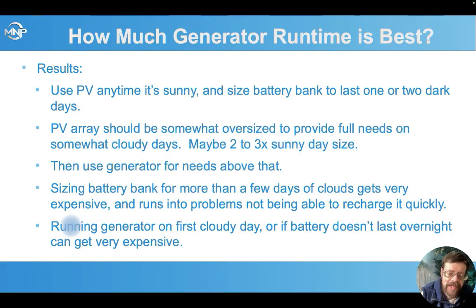that we're running the generator a lot more than we need to, and that's going to lead to a situation I often see in off-grid houses where there's just a line of old worn-out generators sitting out behind the power shed. Every 5 years it's worn out and it's on to the next generator. I've seen ones actually where they've worn out nice prime power generators every 10 years because every morning the generator was running for 3 hours before the sun came back up. So that's a sign that your battery bank is really not large enough and you need a larger battery bank and or more solar power.